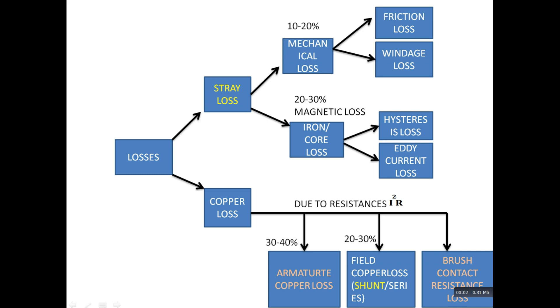Copper loss is due to resistances. It can be from armature resistance, field resistance, or brush contact resistances. Field copper loss is 20 to 30 percent of full load copper losses and can be shunt or series.